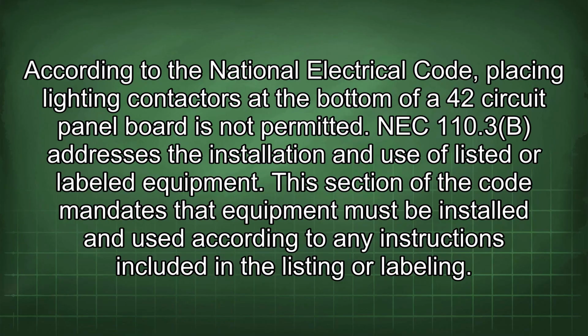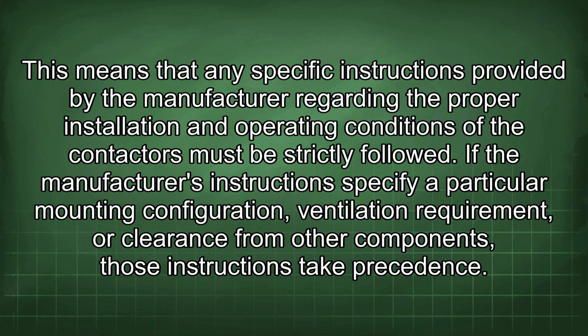According to the National Electrical Code, placing lighting contactors at the bottom of a 42-circuit panel board is not permitted. NEC 110.3(B) addresses the installation and use of listed or labeled equipment. This section of the code mandates that equipment must be installed and used according to any instructions included in a listing or labeling. This means that any specific instructions provided by the manufacturer regarding the proper installation and operating conditions of the contactors must be strictly followed.